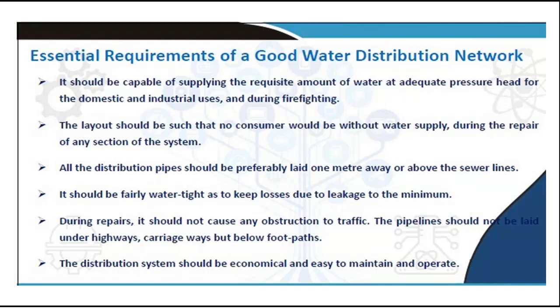your sewage line and water supply line both are very near to each other. If some damage happens to the sewage line, that water may percolate through your water supply pipes. Therefore, they suggest that the distribution pipes should be preferably laid 1 meter away or above the sewer lines. Okay, they should be very far from each other.